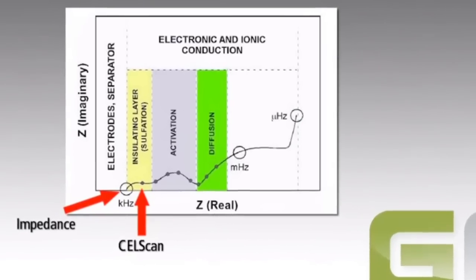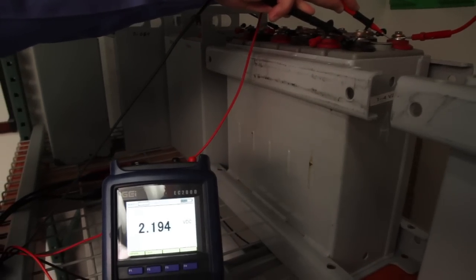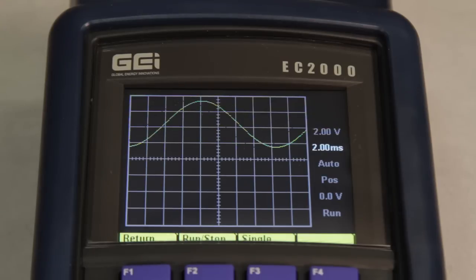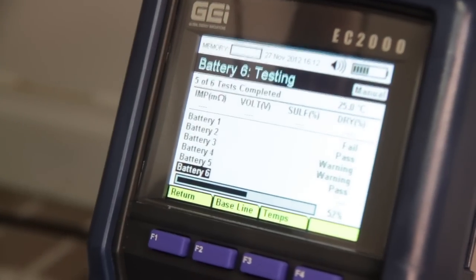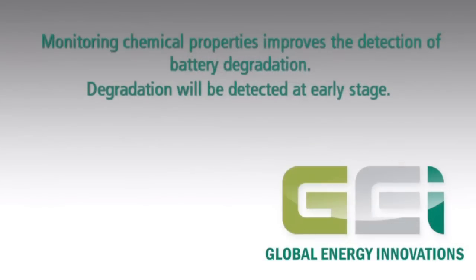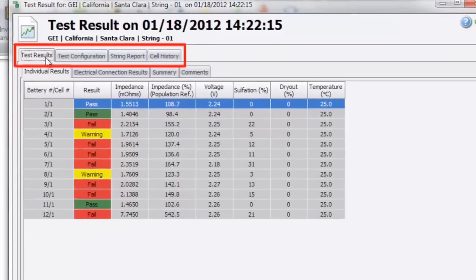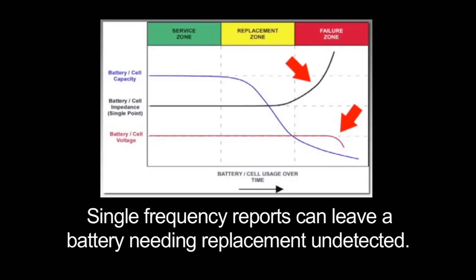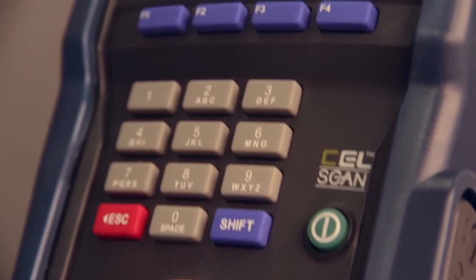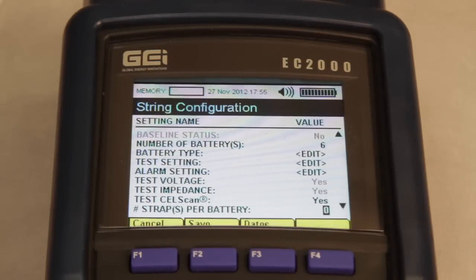The Global Energy Innovations EC Series analyzers probe both real and imaginary components of the battery's impedance over a range of frequencies, providing information about both electrical and chemical properties. Global Energy Innovations' CELScan technology uses algorithms to interpret multi-frequency impedance data in terms of sulfation — the irreversible formation of lead sulfate — and dry-out, the loss of electrolyte. These parameters are leading indicators of degradation phenomena that determine both battery capacity and useful battery life. In contrast, a single-frequency measurement of electrical properties can provide only a lagging indicator of battery degradation, and although batteries in the failure zone may be correctly identified, batteries in the replacement zone will often go undetected.